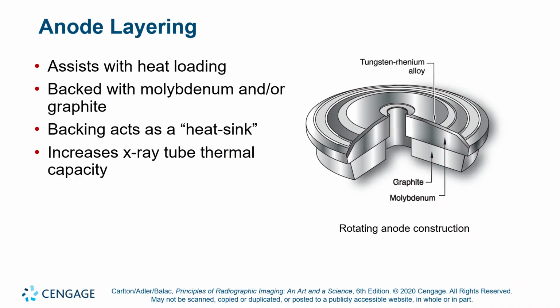All right, anode layering. Again, there's a graphite base or backing. The anode wheel itself is primarily molybdenum, and the focal track is primarily tungsten-rhenium alloy. Okay? So you don't make the whole thing out of tungsten because tungsten is expensive. Molybdenum has a similar heat capacity, but it's much cheaper than tungsten. So typically only the focal track of the anode is made out of tungsten.